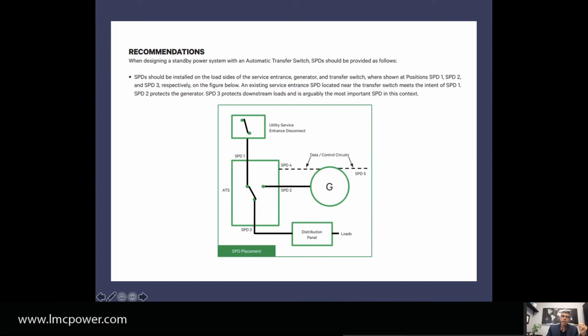At minimum, if this is your automatic transfer switch with electronics inside, and this is your service entrance—from the utility side, if a transient comes in, you want SPD1, a surge protector, at the entrance of the building on the building's panel. That will protect the electronics on the surge and the ATS equipment.